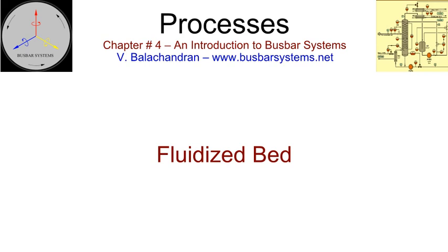The duration of the dip is important as it provides the necessary thickness. Once a bar is taken out of the bed, a jerk ensures that all the excess epoxy on the bus bar falls back into the bed, giving the bar a uniform coat. This process requires skilled operators. The size of the epoxy powder is very critical and it should fall within a band, to ensure bonding. The thickness of the coating to be applied is determined by the voltage rating of the bus duct.